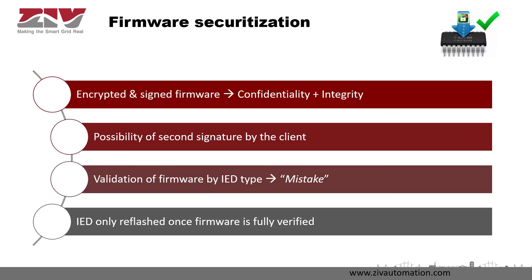Another main aspect of cybersecurity is patch management. Cybersecurity is alive and firmware updates to the IED may be relatively frequent, so firmware securitization is a key factor. The firmware of the IED is encrypted and digitally signed by ZIV, which guarantees the confidentiality and integrity of the firmware. Additionally, the final client is offered the possibility of also signing the firmware for more security. The IED validates both signatures and also validates the firmware by IED type — it is not possible to upload firmware of one IED type to another, which avoids mistakes during the upload process.